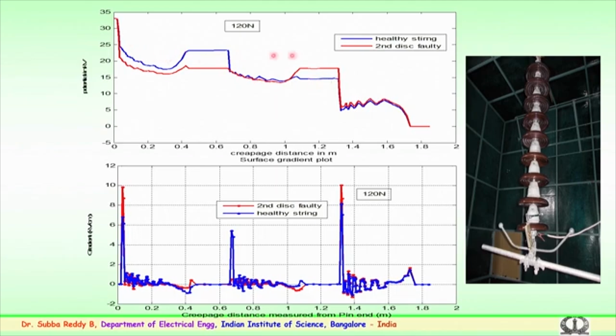This blue one is for the normal healthy string. What we call healthy is that none of the discs in the string are faulty. What happens in case there is a faulty disc in the second position? You can see the red curve here, 33 kilovolts is the first pin or line end. Once the second disc is faulty, the potential comes down and you can see the rise in potential at the third disc. This rise in potential will cause a potential difference or a field effect, which will be a very serious threat in case of strings containing a number of discs for 400 kV and 765 kV, which we will be observing.